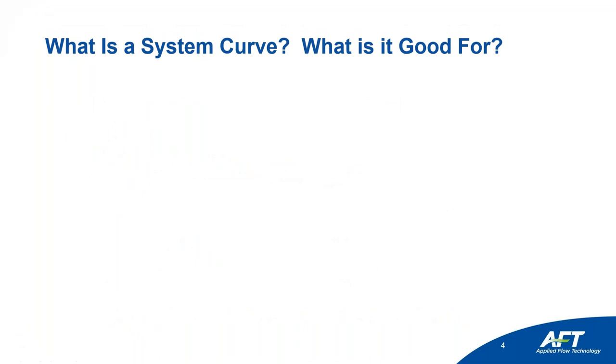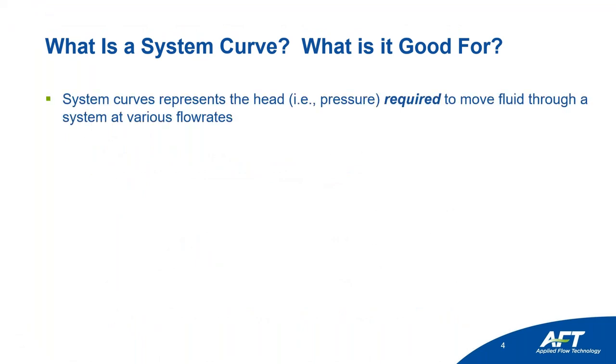So what is a system curve and what is it good for? How is it useful for you? System curves represent the required pressure increase in order to drive a fluid through your system at various flow rates. And so when you're dealing with pumping systems, it's really useful to use head instead of pressure, and volumetric flow rate to quantify your system curves.